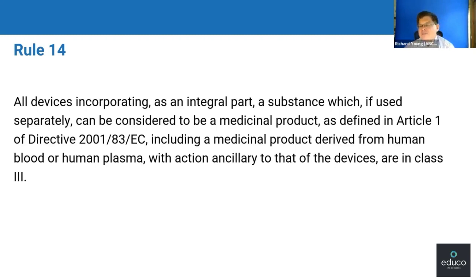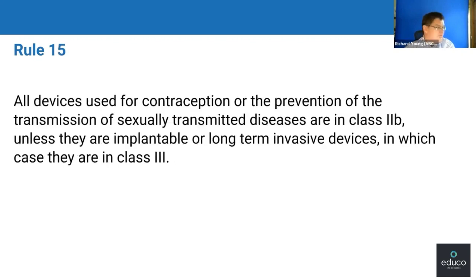So you've got to be very careful about what you add in with products and whether they are pushing it into this category. And there's a series of rules around the incorporation of medicinal products into these sorts of products, and how you have to relate to your notified body with that. Fairly complicated. If you have got these materials, really delve into that a little bit more with your regulatory department.